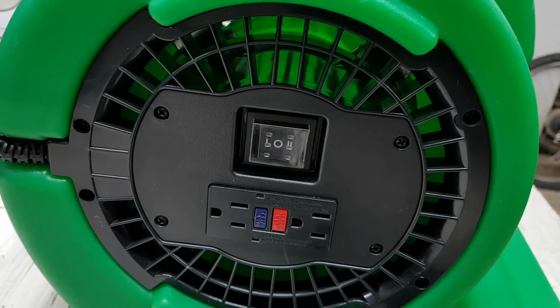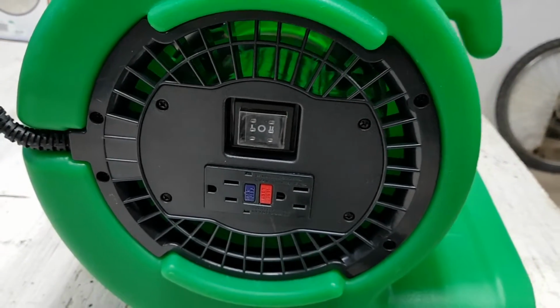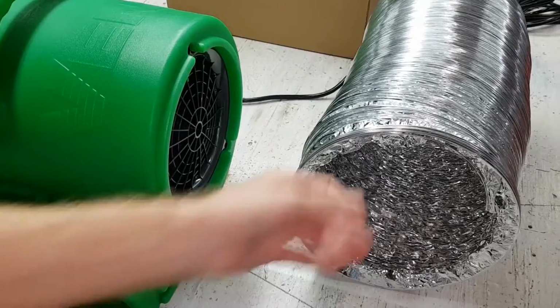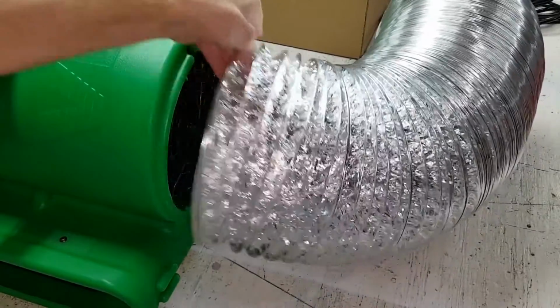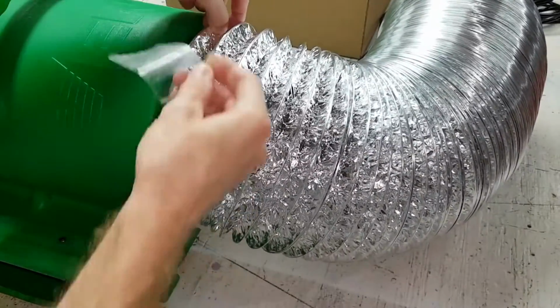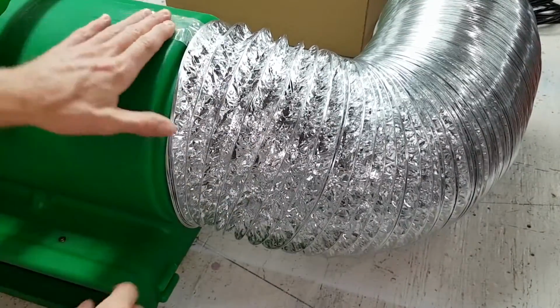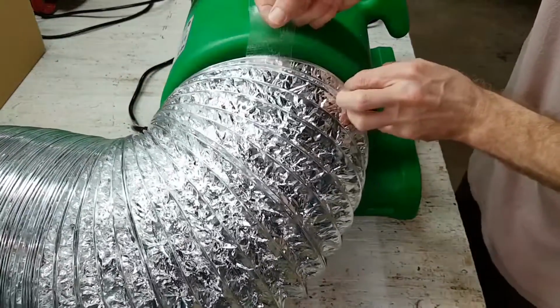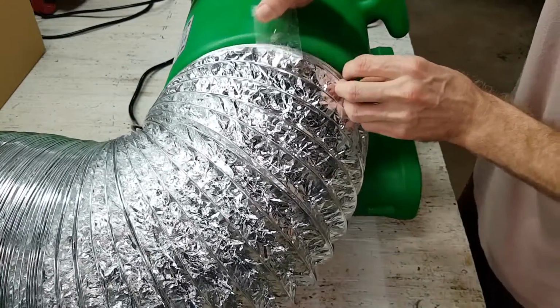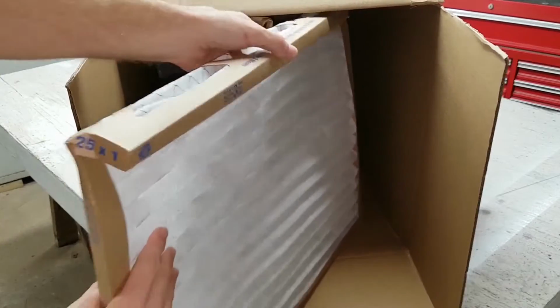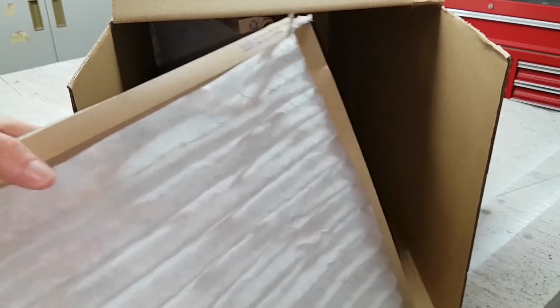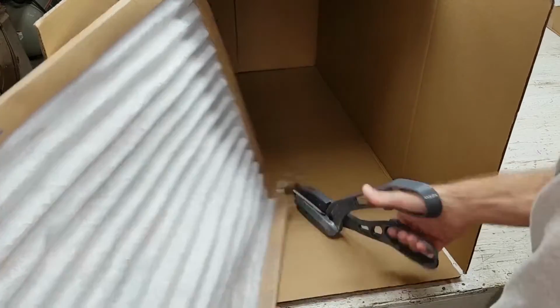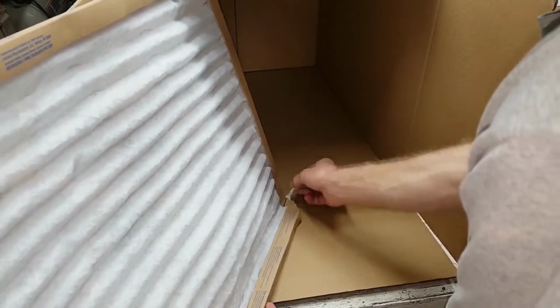I believe piping the blower to a separate filter box might be a little better in regards to fire safety. That way the blower motor would be operating outside of any flammable cardboard box in the system. Two separate pieces of the 10-inch diameter foil ducting must be used to connect this kind of blower because of its dual inlets. The furnace filters in the box are reoriented because two outlets are needed for the blower.